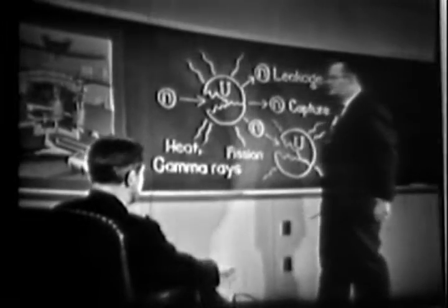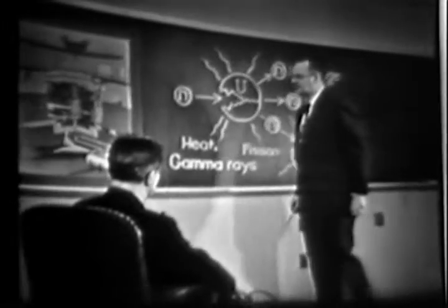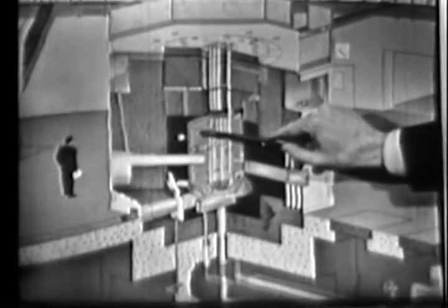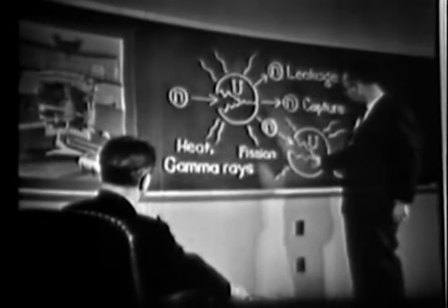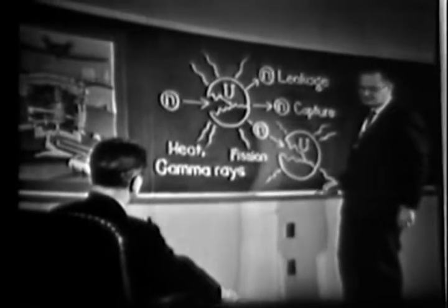Can you tell me how you start the reaction? We find it most convenient to vary the capture rate in order to control a nuclear reactor. A strong absorber of neutrons, cadmium, in the form of blades, passes in between the rows of fuel elements in the water in the core. To start the reactor up, these elements are pulled out of the reactor. Simultaneously, a weak neutron source causes the initial fissions. Because we've reduced capture, there are more neutrons available for subsequent fissions, and quickly the neutron density builds up to the design operating level.